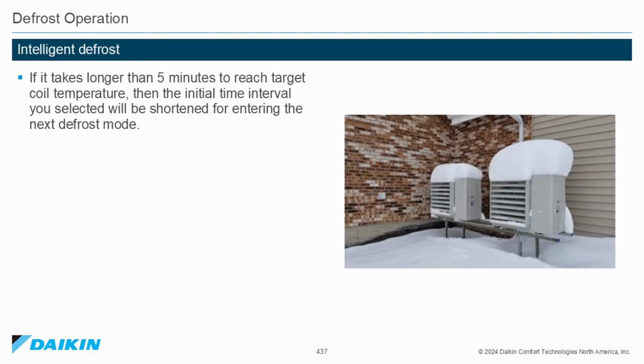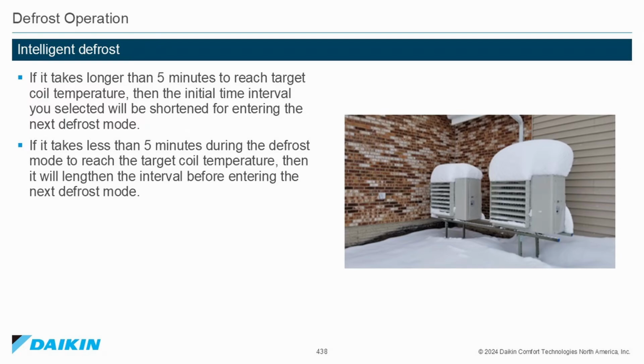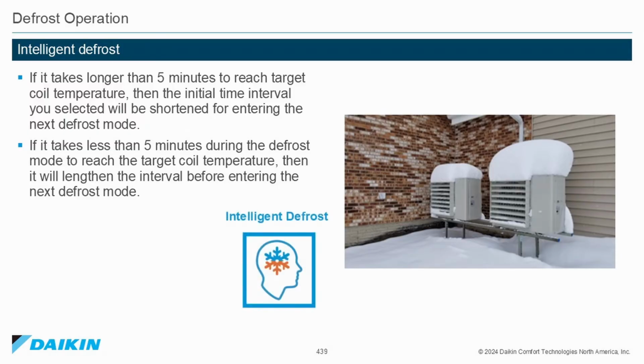If it takes longer than 5 minutes to reach the target coil temperature, then the initial time interval you selected will be shortened for entering the next defrost mode. If it takes less than 5 minutes during the defrost mode to reach the target coil temperature, then it will lengthen the interval before entering the next defrost mode. This is called intelligent defrost.